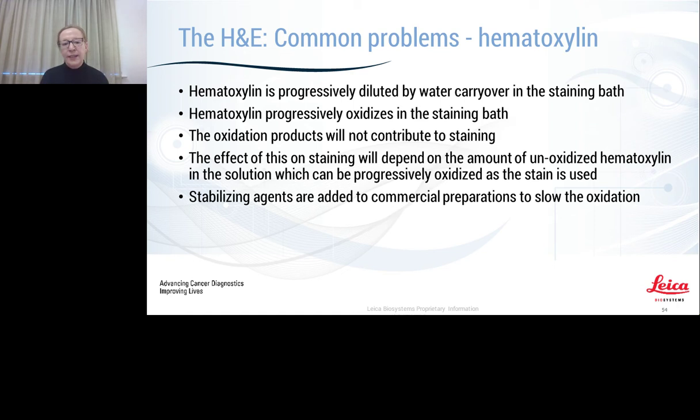The other thing to consider is that nowadays most labs use automated stainers. So whatever the recommendation from the manufacturer on either the stainer or the hematoxylin itself, think about what they recommend in terms of times and protocols, because the design of the stainer, the size of the surface area that is available for oxidation of the reagent, will contribute to how long that hematoxylin will last on the instrument.